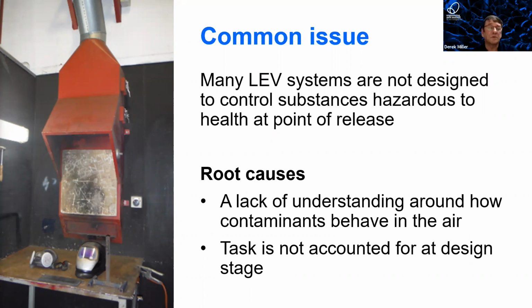The problem is a lot of these systems aren't designed to control—I think people just find them cool-looking sometimes. If we look at that red system on the left, that's a purpose-built system here in New Zealand at a trade training establishment for metal workers, designed to capture fumes from brazing and welding. But whoever designed it doesn't understand how these substances are actually released. When we test it, we find it's only effective 1 centimetre away at the bottom, so you'd have to be welding or brazing hard up against the wall for it to actually capture the contaminant.